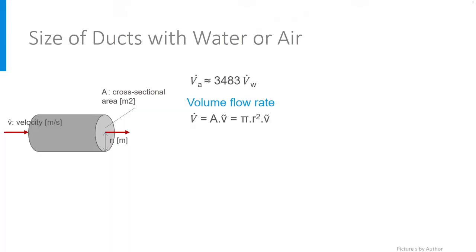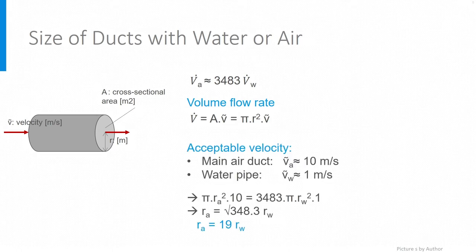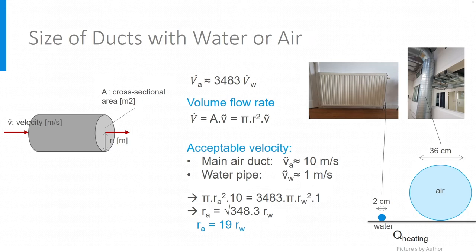What does that mean for the size of the ducts? The volume flow rate of a fluid equals the cross-sectional area of the pipe times the velocity of the fluid, or π × R² × velocity, where R is the radius of the pipe. Because of noise and pressure, it is better to limit velocity in ducts: in a main air duct, the velocity will be around 10 m/s, while in a water pipe it will be around 1 m/s. Using these values, the radius of the air pipe should be 19 times that of the water pipe. In general, a water pipe from boiler to radiator has a diameter of about 2.5 cm, while an air duct transporting the same quantity of heat needs a diameter of 36 cm.